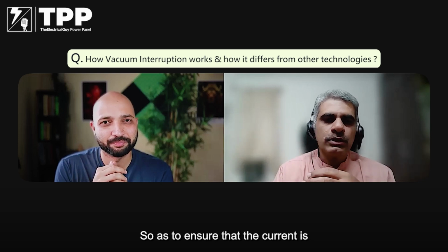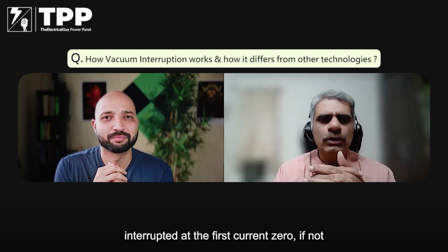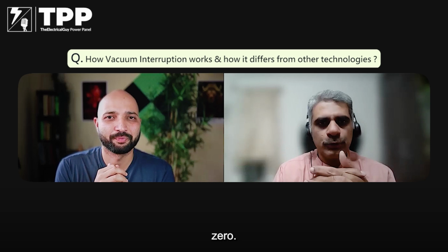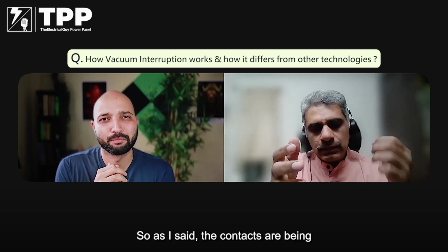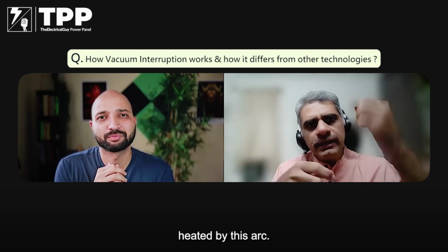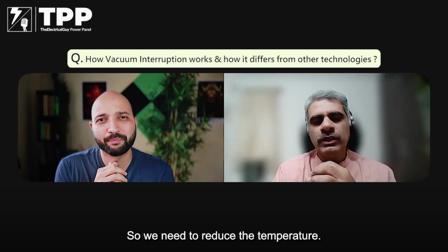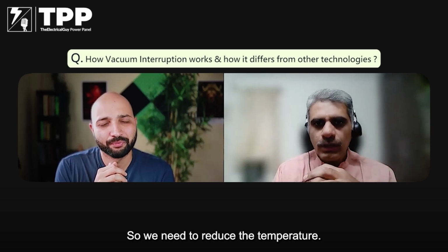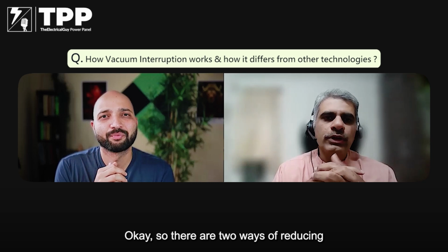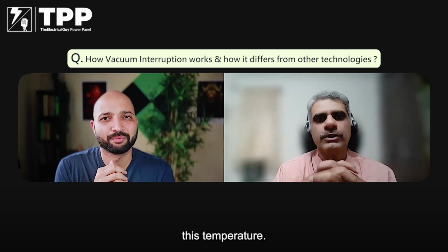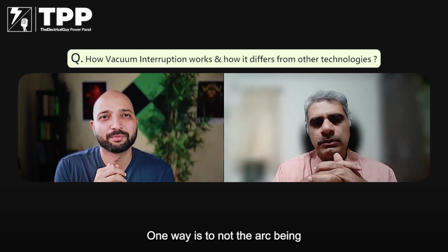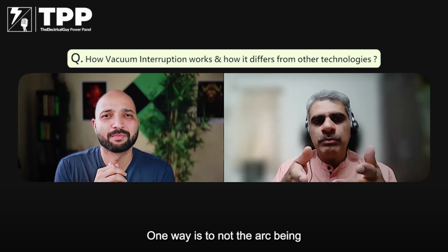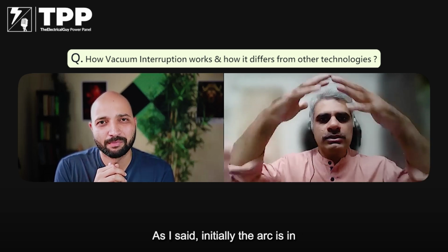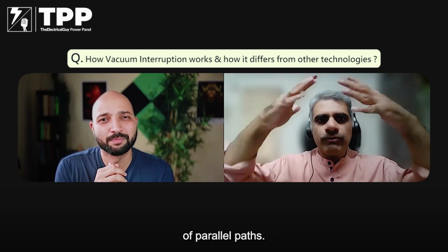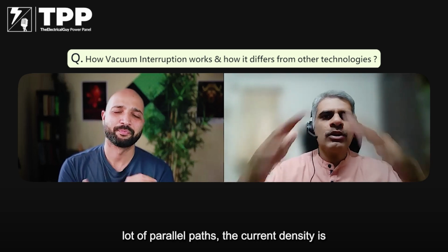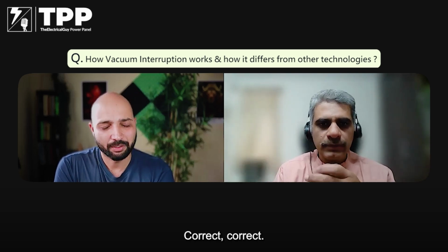So as to ensure that the current is interrupted at the first current zero, if not at the first, at least at the second current zero. So as I said, the contacts are being heated by this arc. So we need to reduce the temperature. Okay, so there are two ways of reducing this temperature. One way is to not let the arc be constricted. As I said, initially the arc is in the form of a shower with a lot of parallel paths. And as we know, if there are a lot of parallel paths, the current density is lower, isn't it? Correct.